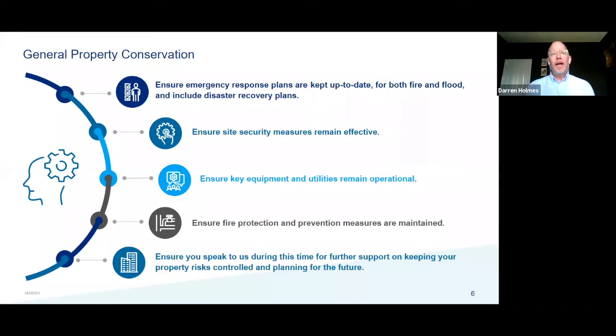Also think about the isolation of non-essential electrical and water supplies - can these be cut off? On water supplies specifically, there are some concerns around water standing stagnant in pipes. During this lockdown, systems won't be flushed or run, and checks probably won't be carried out by any supplier for Legionella and Legionnaires' disease. So I would consider shutting down and draining water supplies if that's possible.